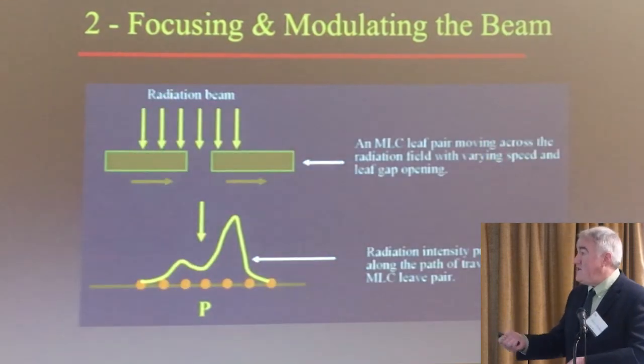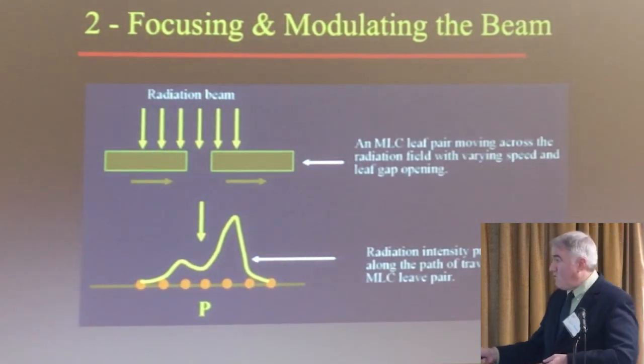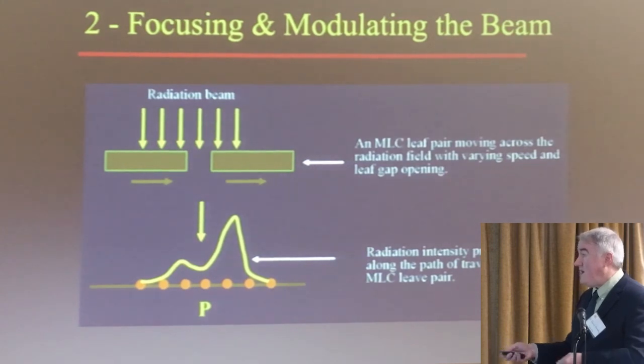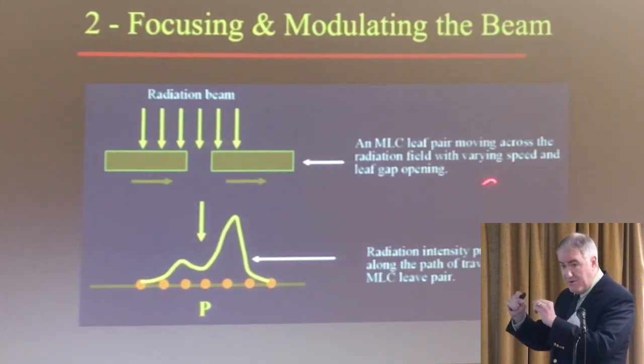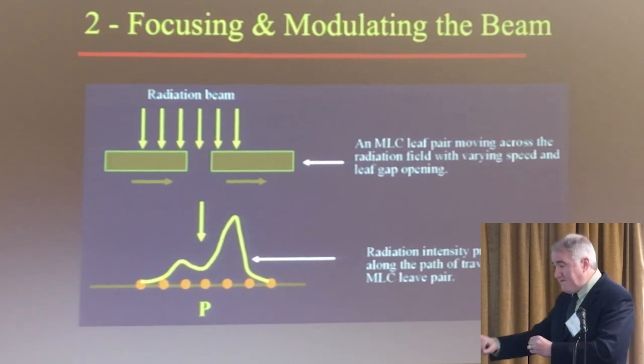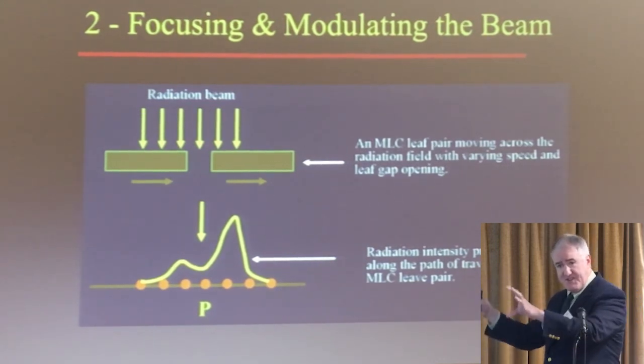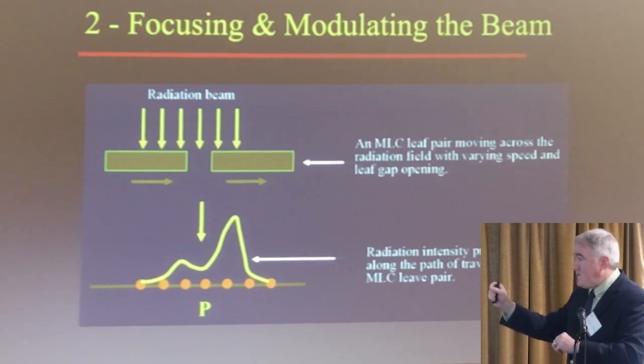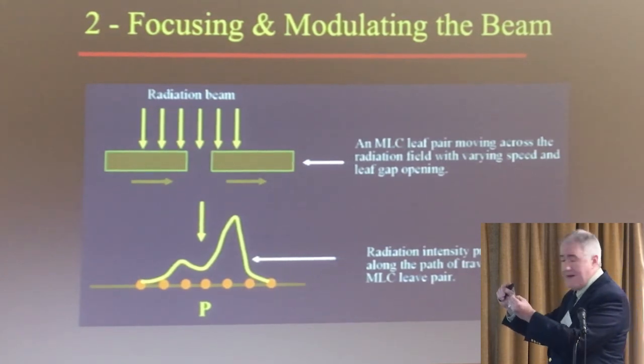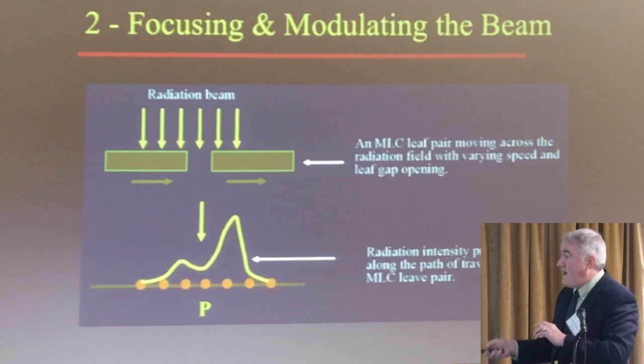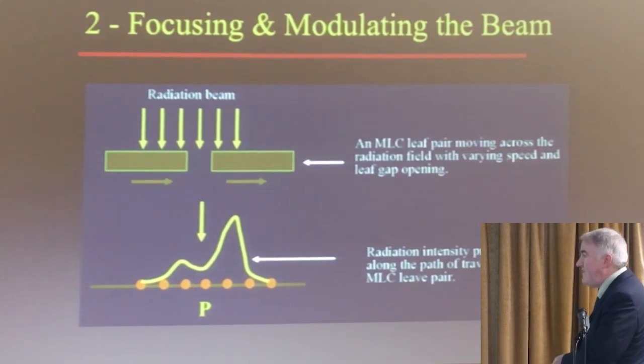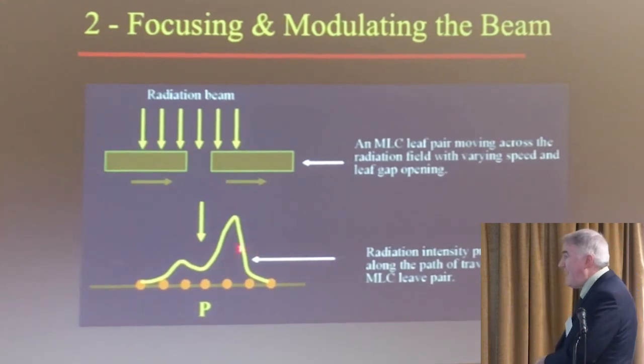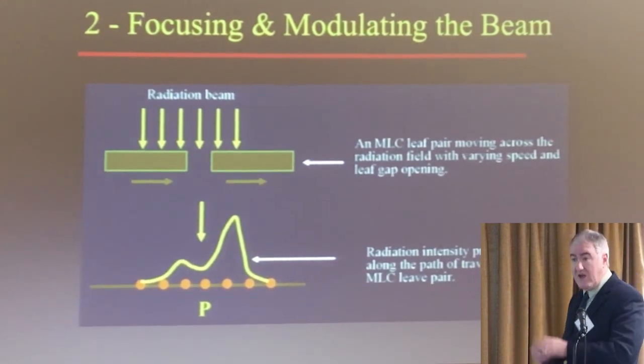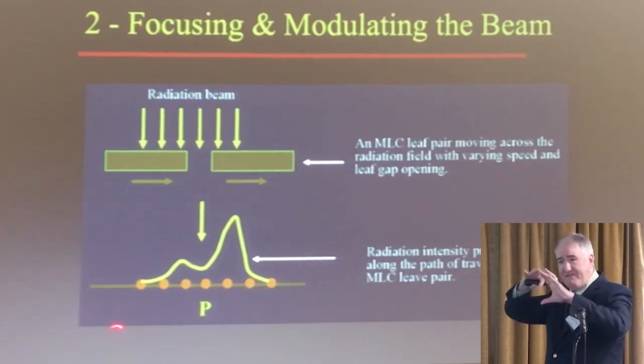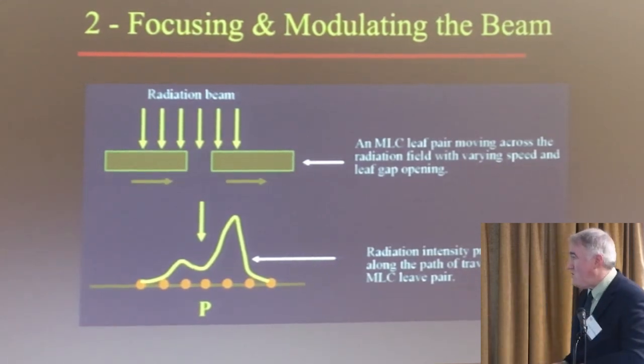Where that has developed into is that you can actually use that effect where you've got a radiation beam coming up and down here and you've got these collimators, and you can move them at different rates. If you turn on a flashlight, everything in front of you is getting the same exposure. But if you can modulate the beam, if you can slowly move these apertures across the radiation beam, but stop and let it sit at this level right here for a little bit longer than it does over here, then you can modulate the beam. You can give a higher dose of radiation here than we're giving over here. And that allows you to suddenly get very creative and shape the radiation exposure in a three-dimensional way.